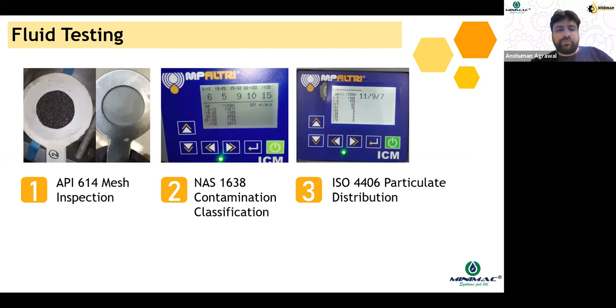The second standard is NAS 1638, which covers the testing of micron-level particles, as low as 5 micron. The last one is ISO 4406, particulate distribution, which is again an international standard from ISO. It counts the particles more than 4 micron in size. There are particle counters which can be used in both online and offline modes for doing the inspection of NAS as well as ISO.